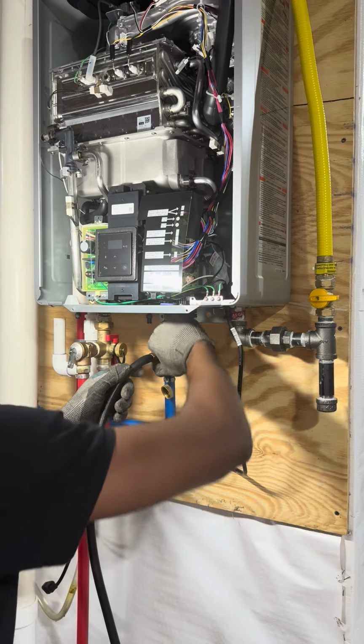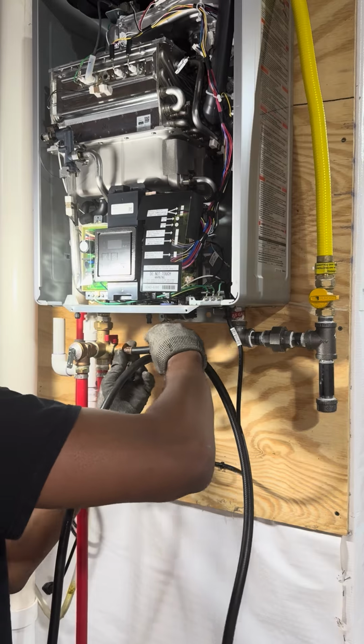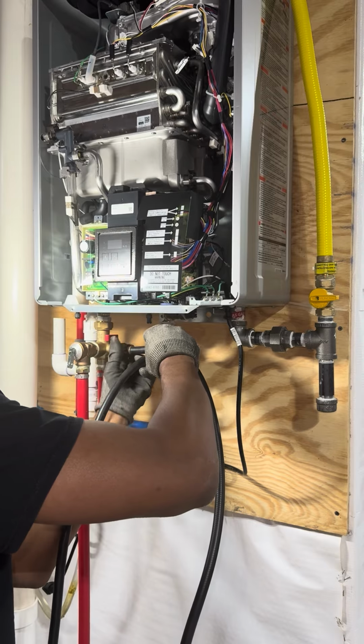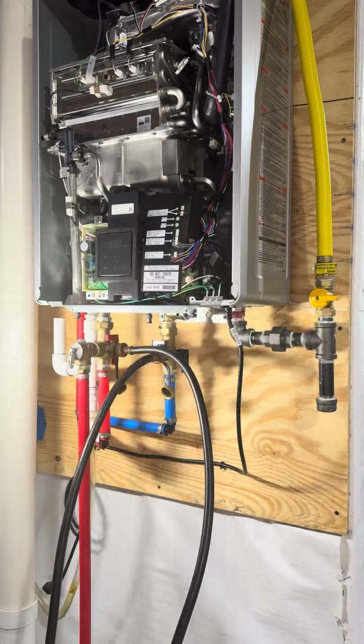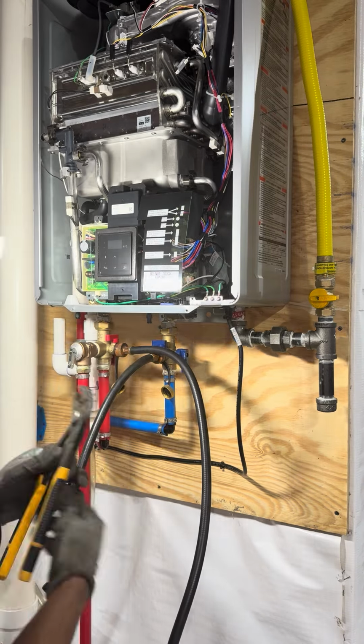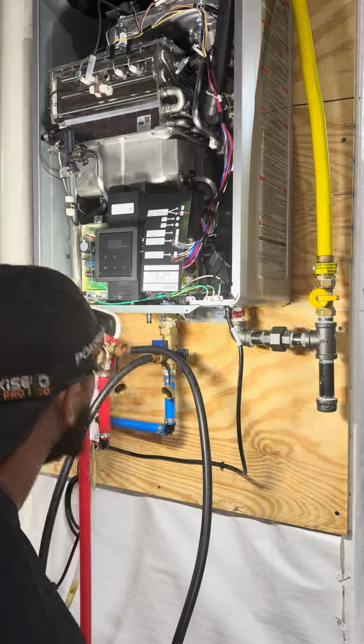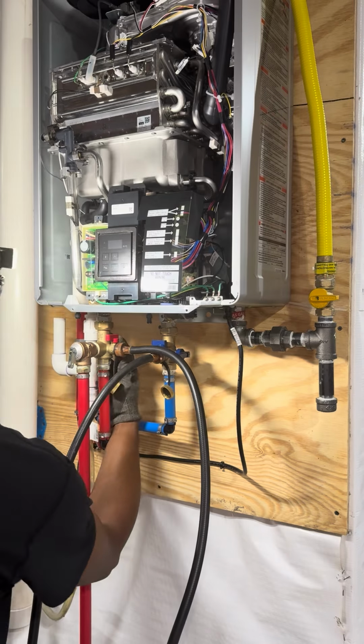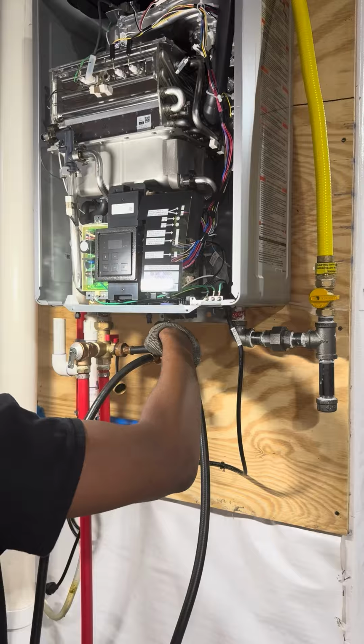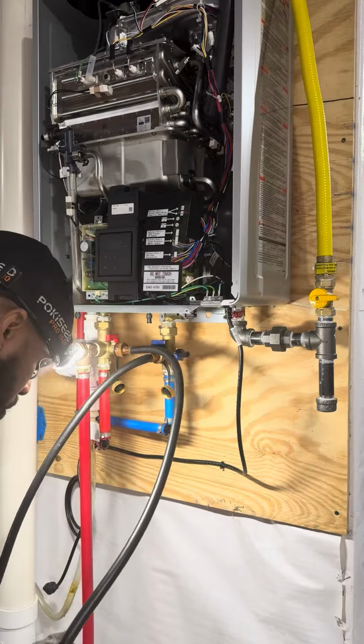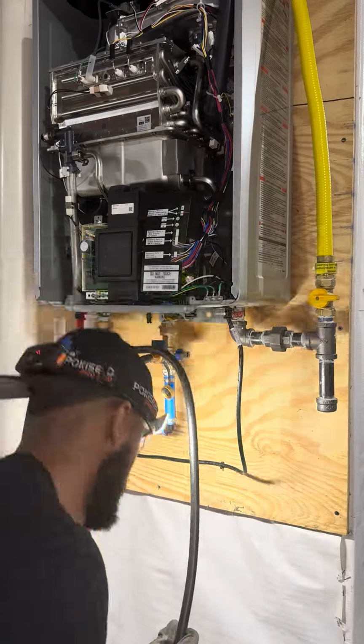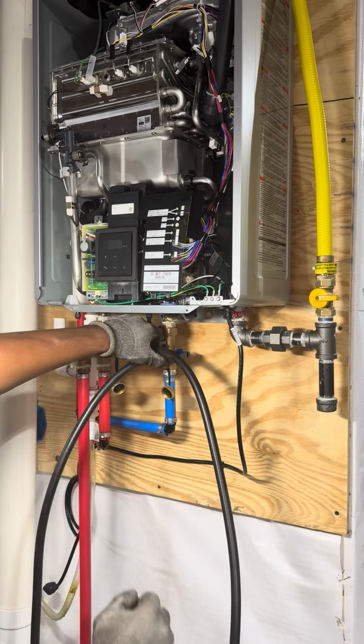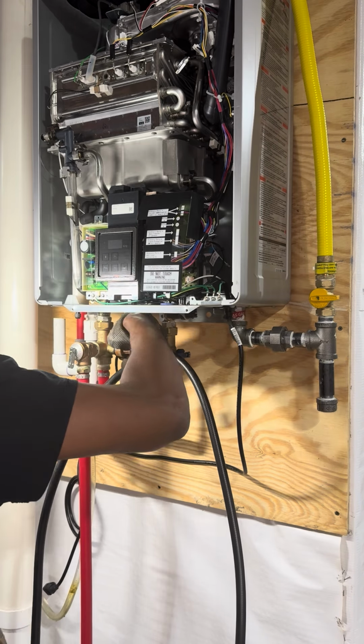So now I'm putting my hose on the supply side and then the return side, and tightening it so no water drips on the floor. Then I close the supply and return, and open up the service ports so I can drain out the heat exchanger.